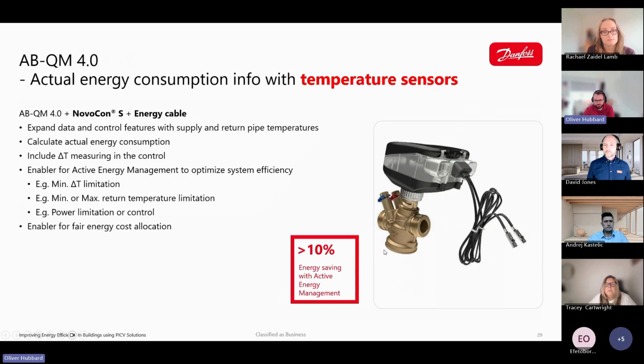So here we have the ABQM with the NovoCon actuators. It expands data and control capabilities by measuring supply and return pipe temperatures with the probes here, and calculates actual energy consumption and integrates the delta T measurements into the system control as well. It also has active energy management features, which enable optimization of the system efficiency, including minimum return temperature limitation, power limitation or regulation, and supports fair energy cost allocation across users of certain zones within a building.